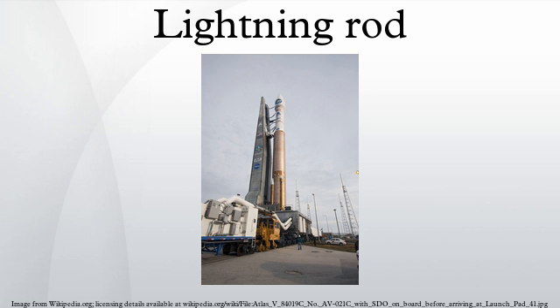The air terminals are typically arranged at or along the upper points of a roof structure, and are electrically bonded together by bonding conductors, which are connected by the most direct route to one or more grounding or earthing terminals. Connections to the earth electrodes must not only have low resistance, but must have low self-inductance.